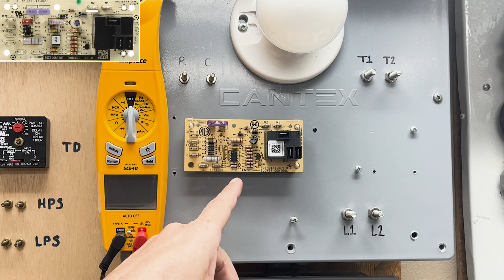It's L1 and L2, and we have 24 volts up here between R and C. Our objective is to bring the load on through the blower control board. We do need to get a live 240 volts of electricity between T1 and T2 to get this load to activate. This is just a 120 volt light bulb.